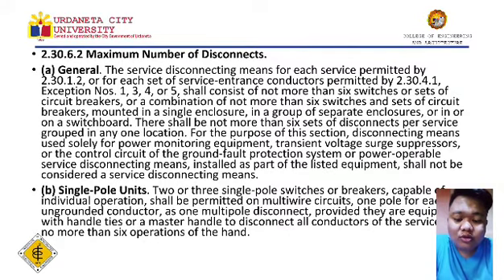For the purpose of this section, disconnecting means used solely for power monitoring equipment, transient voltage surge suppressors, or the control circuit of the ground fault protection system, or power operable service disconnecting means installed as part of the listed equipment, shall not be considered as a service disconnecting means. B. Single pole units. Two or three single pole switches or breakers capable of individual operation shall be permitted on multiwire circuits, one pole for each ungrounded conductor, as one multipole disconnect, provided they are equipped with handle ties or a master handle to disconnect all conductors of the service with no more than 6 operations of the hand.